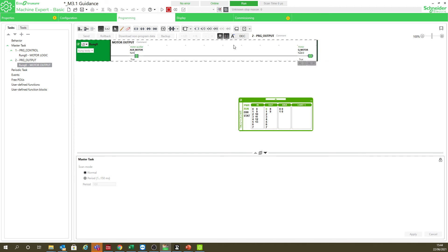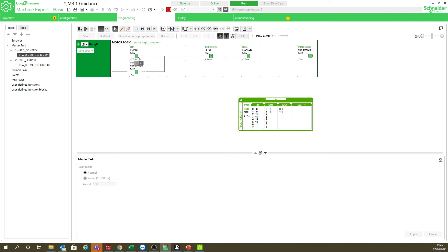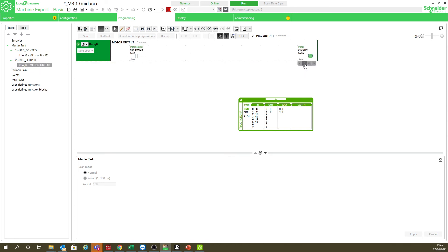You need to be careful. In the output, as you can see, if you leave the force this part doesn't make sense — because you have a 1 here, it should be 1, but we are forcing this value. In the output you can see there is False. Even if you write a value it will be overwritten. If you force it, it will be 1 because it doesn't really care in that case. But you should be aware of the difference between writing and forcing a value in your code.